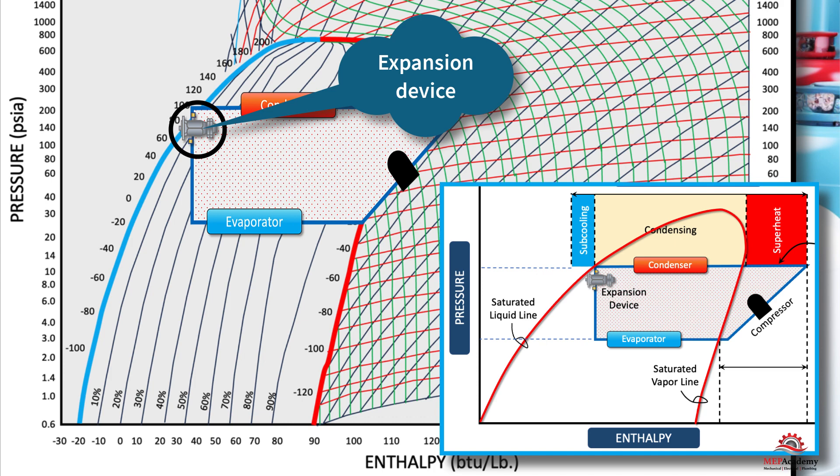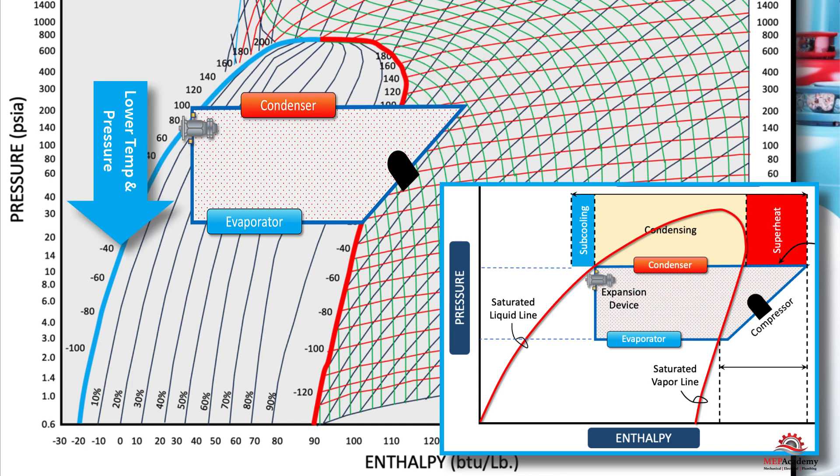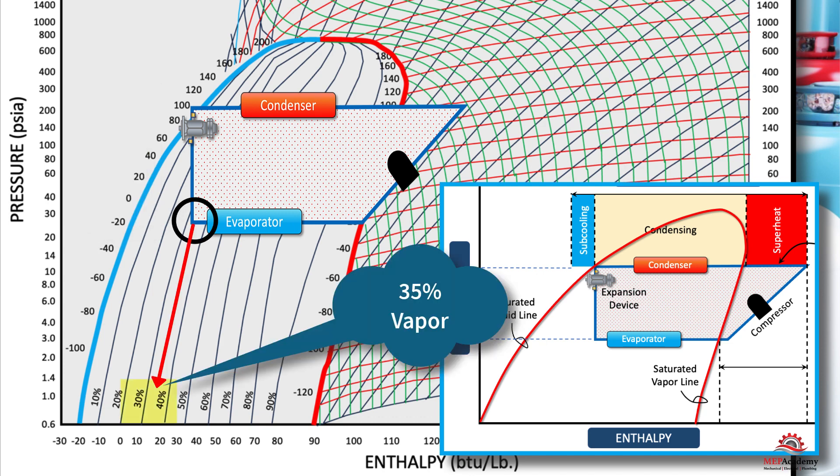As refrigerant pressure is related to temperature, as the refrigerant liquid enters the expansion device some of it flashes causing the temperature to lower. You can see that at the entrance to the evaporator a certain percentage of the refrigerant has already been evaporated and turned into vapor, approximately 35% in our example.